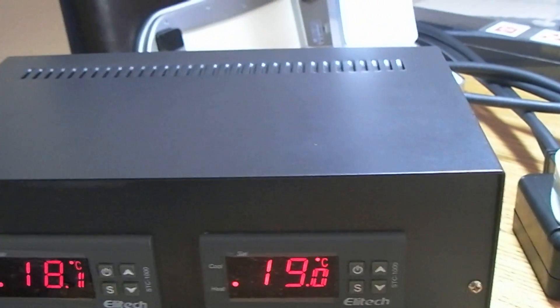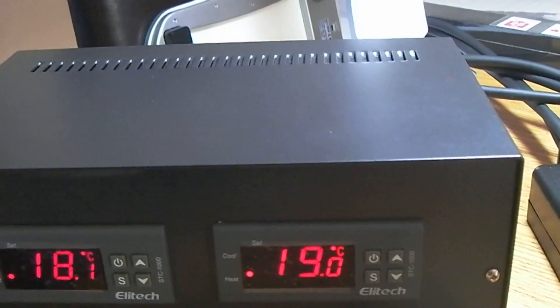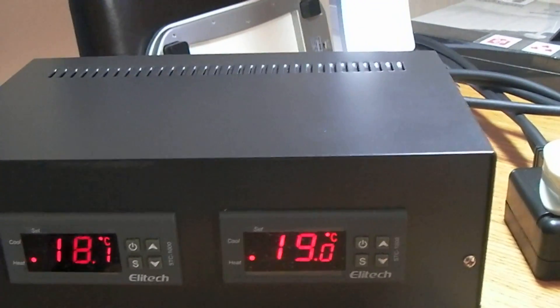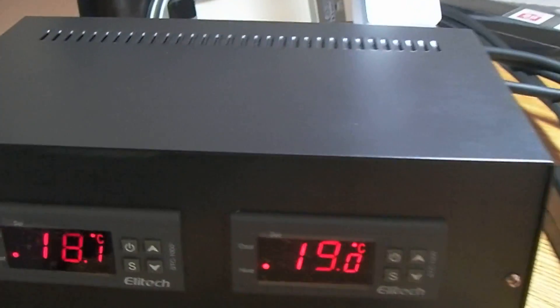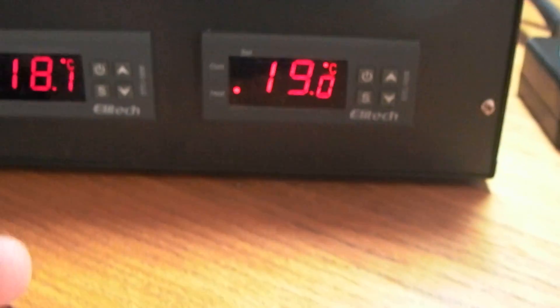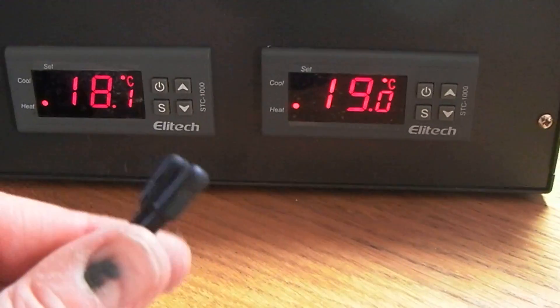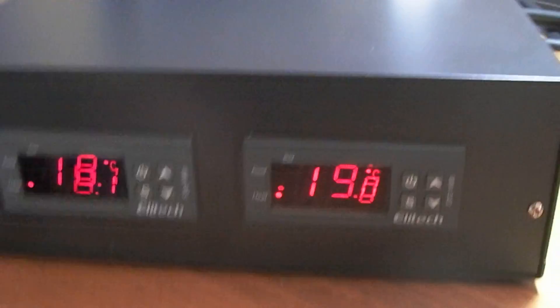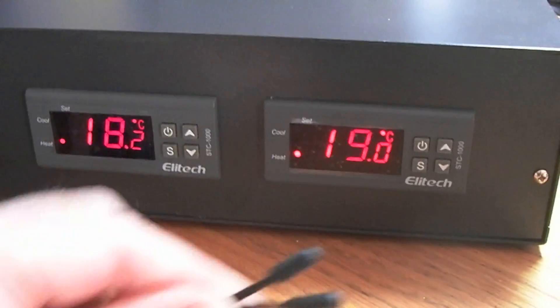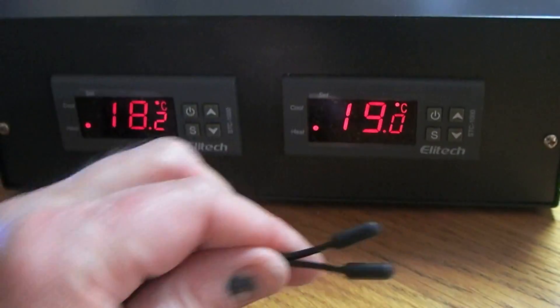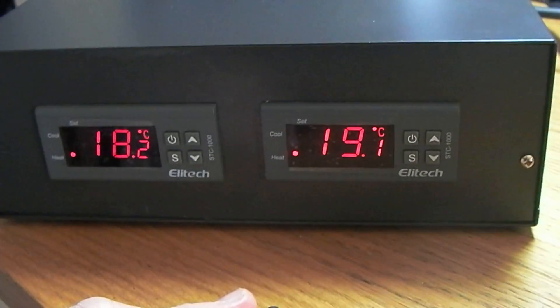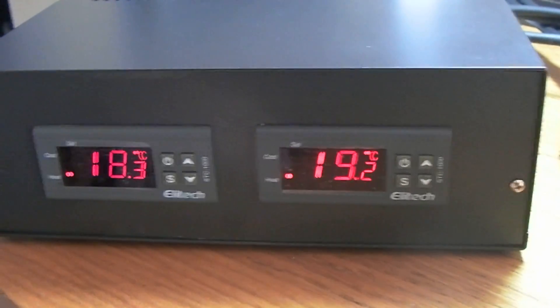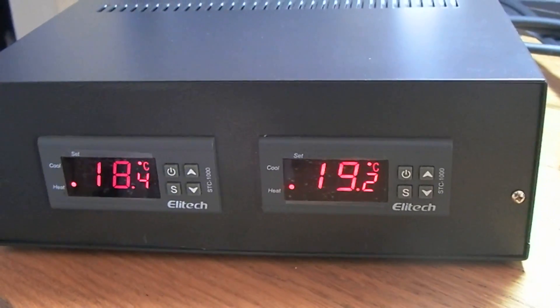And I guess we're pretty much done. I noticed about a half a degree difference between the two probes. They're in different places at the moment, that's why you've got a bigger gap. But if we keep them together... In fact I tested this overnight. I just put them together on the table like that, and there was 0.4 to 0.5 of a degree difference.